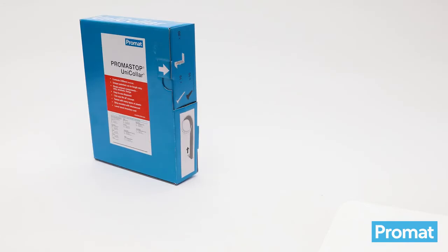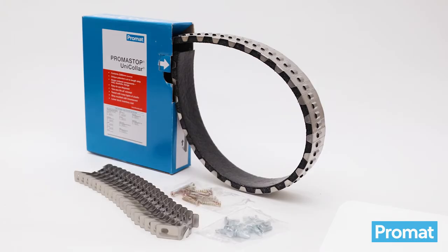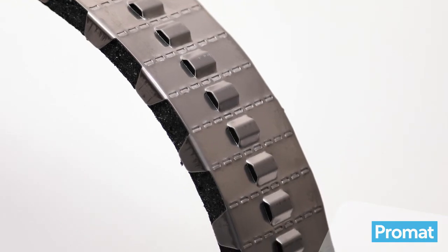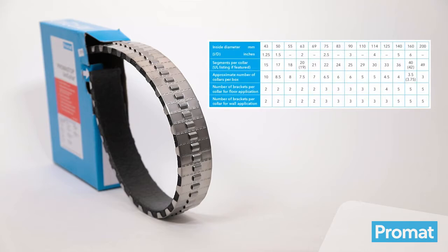Each Promastop UniCollar is packed in individual boxes, each containing 2250mm length of collar or 150 segments, including fixing accessories. The collar is designed so that it can be cut and snapped in modules of 15mm. For a guide to the approximate number of collar sizes per strip, please refer to the user guide table located on the top of the box.